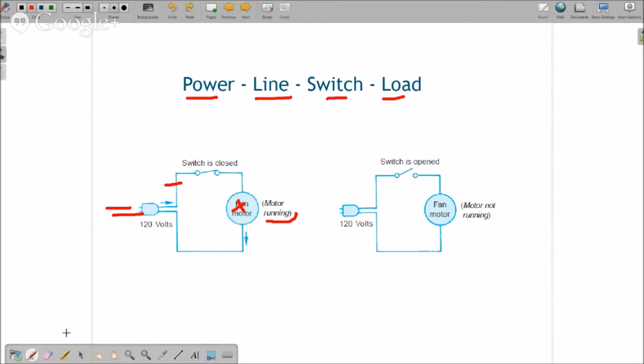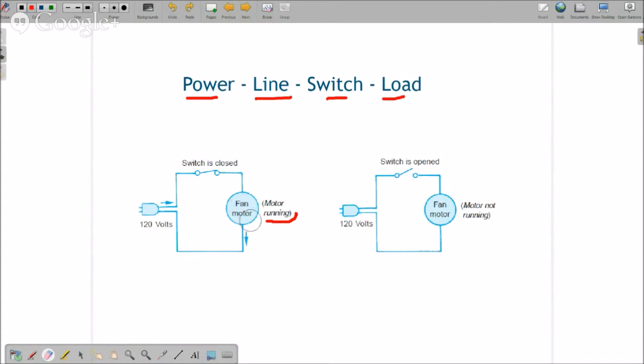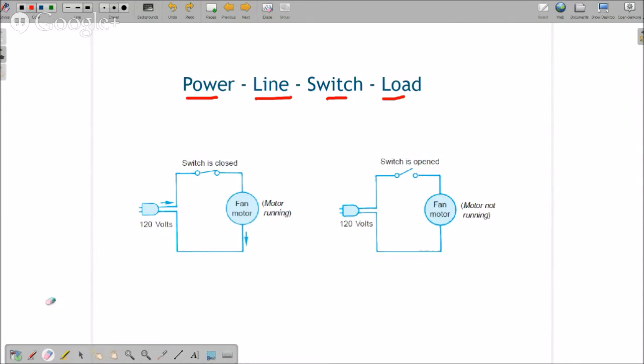It doesn't have the power it needs. The line or the wires are broken or corroded. The switch is either not closed or burned out, or the load has failed. So that's it. So now you have to just figure out what part of the circuit is what based on the schematic diagram. And then it's a matter of checking power, the line, the switches, and the load.